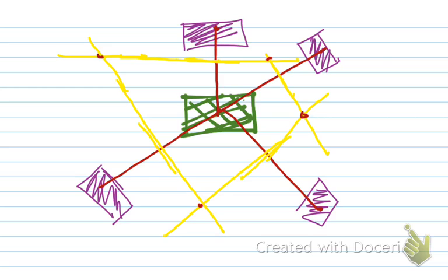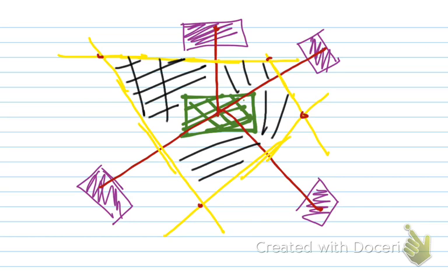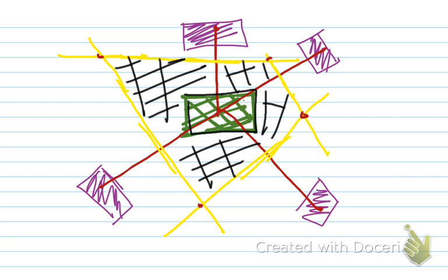An area is marked by these lines—the area enclosed by these lines. The area shaded in black is that area that is going to be served by this proposed substation. Using this perpendicular bisector method, you can see how much area the proposed substation can serve.